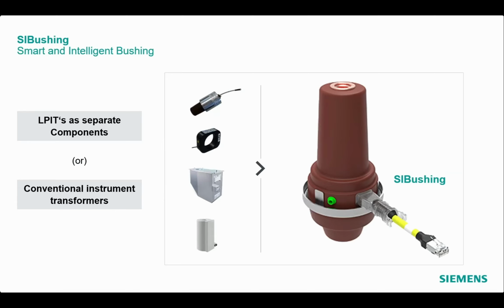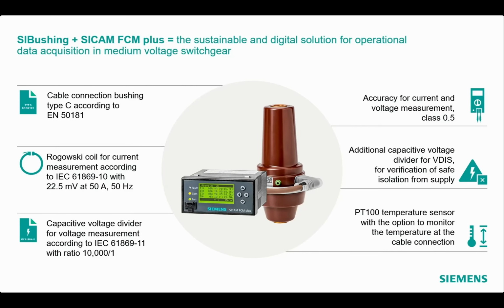As announced, I would like to explain now the SIBushing in detail. SIBushing combines current and voltage measuring in the cable connection bushing and avoids a project-specific configuration of external instrument transformers. SIBushing is a smart and intelligent cable connection bushing, type C, with an integrated Rogowski coil to measure the current and a capacitive divider to measure the voltage. Both are designed to the instrument transformer standard IEC 61869, providing 22.5 mV at 50 Hz at 50 amps for the current measuring and a transition ratio of 10,000 to 1 for the voltage measuring. The measuring accuracy for voltage and current measuring is class 0.5.